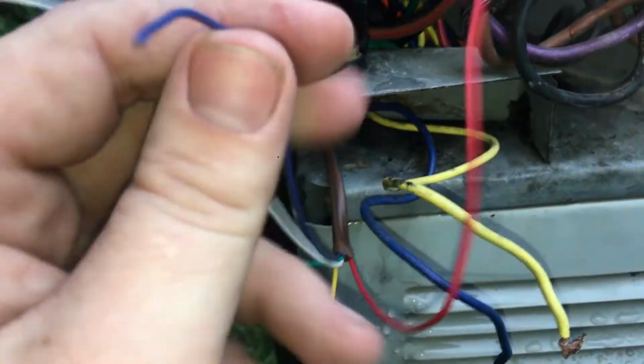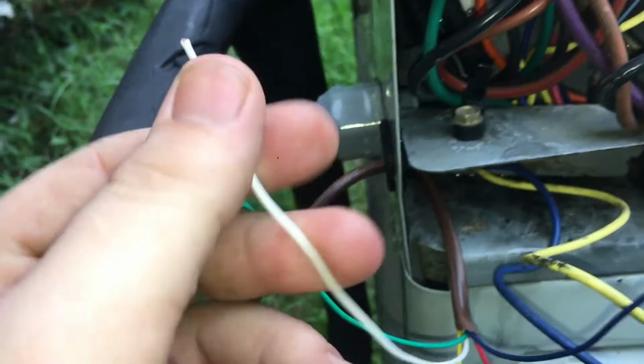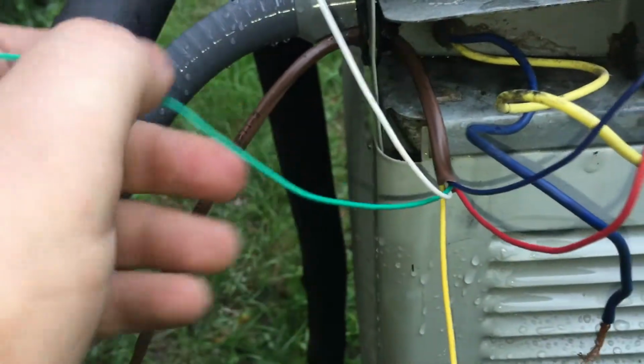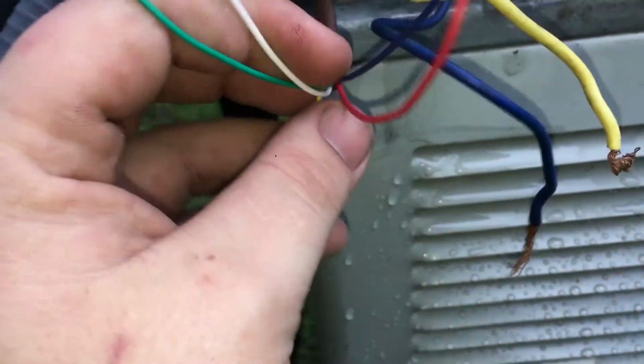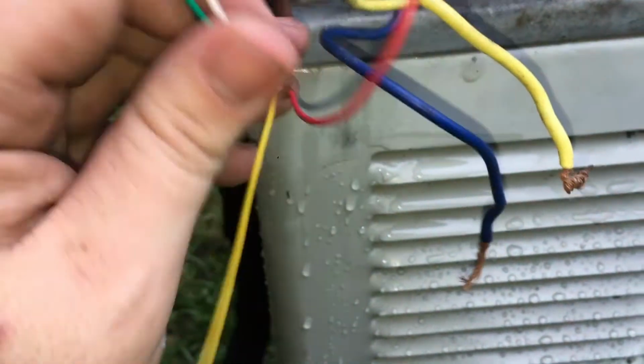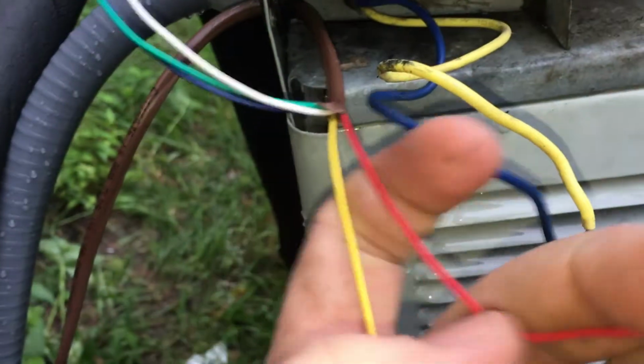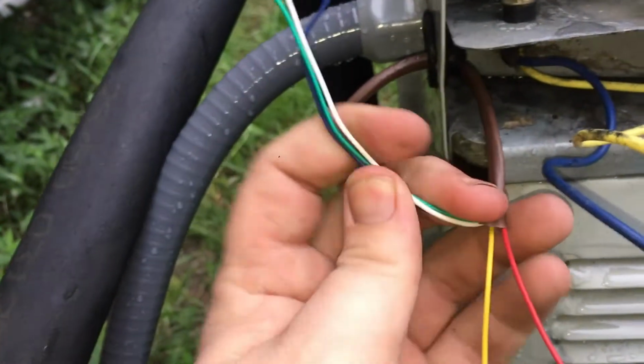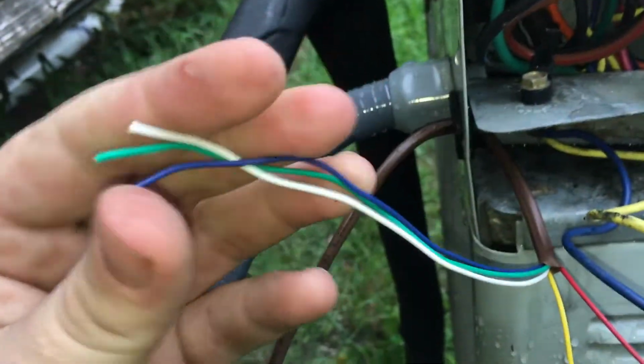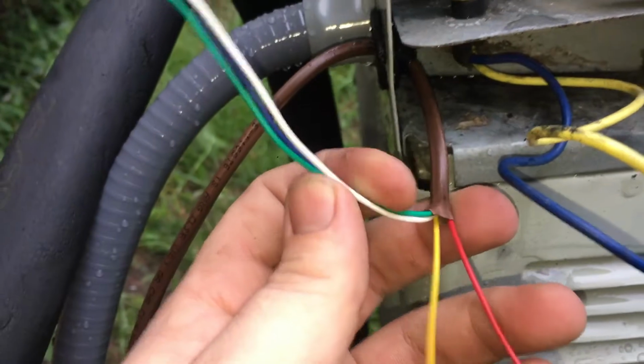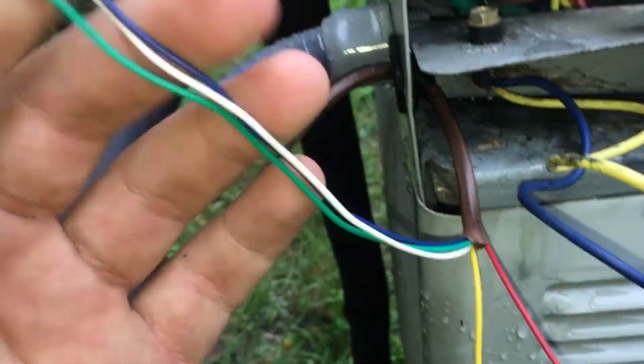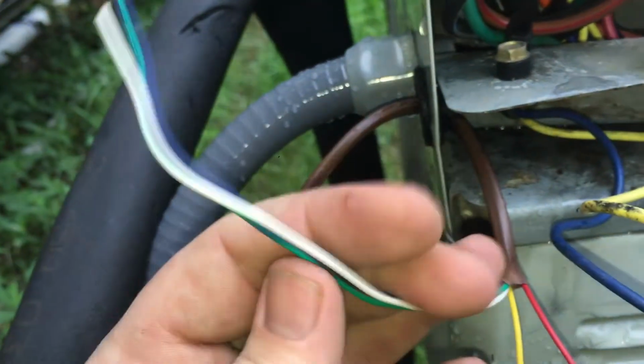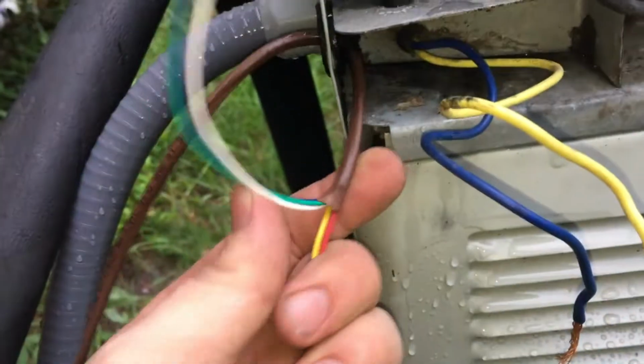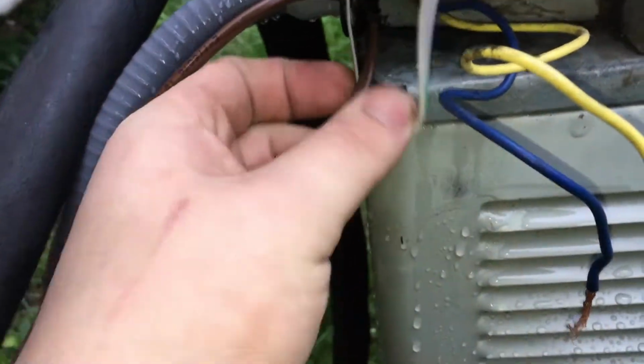Color codes are red for hot, blue for neutral, white for heat, green for fan, yellow for cooling. On the condenser unit, all you need is the red and the yellow, but I would highly recommend not cutting the additional wires off, so that later on if you were to install a heat pump or a communicating unit that needs these extra wires, they'll be there for that. So just take them and wrap them around.